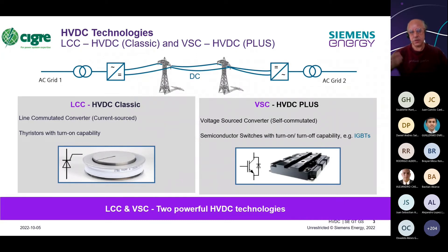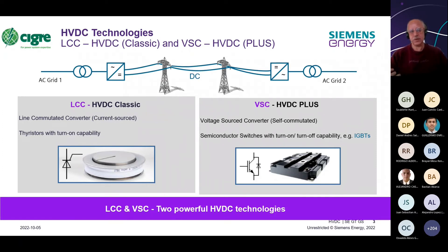HVDC is generally applied for bulk power transmission over long distances, where it provides cost advantages compared to AC transmission. It also reduces the right-of-way requirement, meaning the line corridor is much smaller for a given amount of power. This results in both capital expenditure savings and operational expenditure savings due to lower losses.